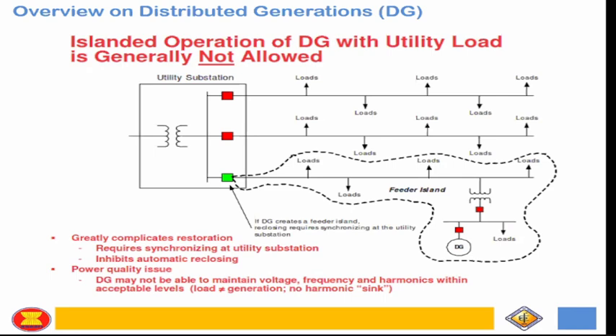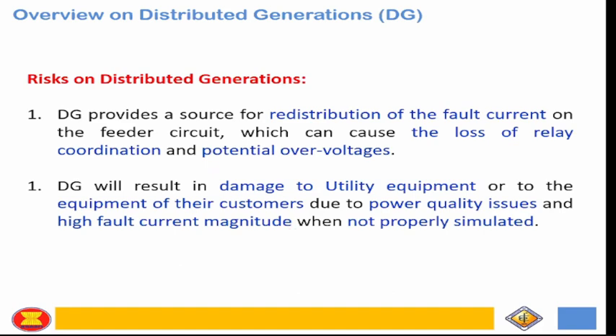And on the other hand, if the generation is lesser than the load, of course there is an abrupt loading. It's like a vehicle: if you abruptly give it a load, its speed will slow down. And while the speed is directly proportional to the frequency, there's an under frequency in that scenario, as well as under voltage. So there's a power quality issue because of the mismatch of the generation and the load. Okay? So what's the other risk on distributed generation?